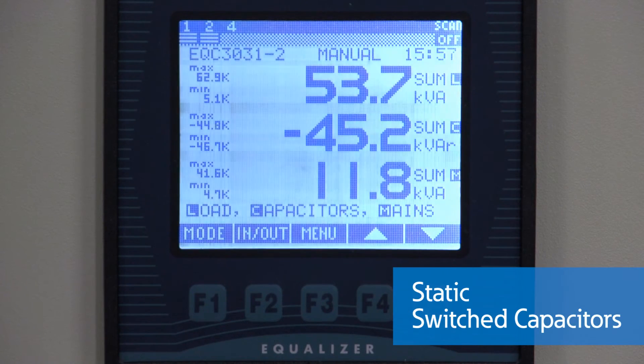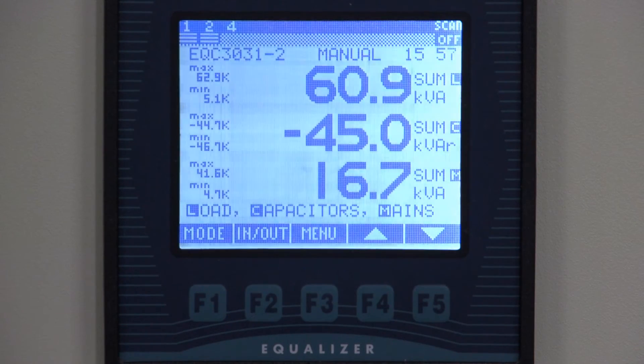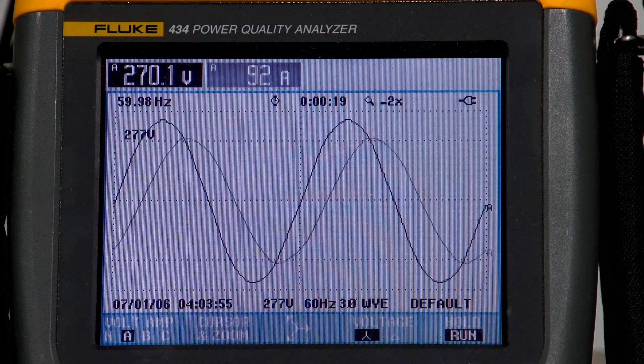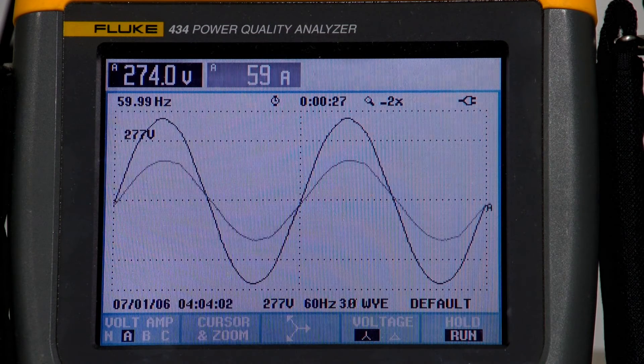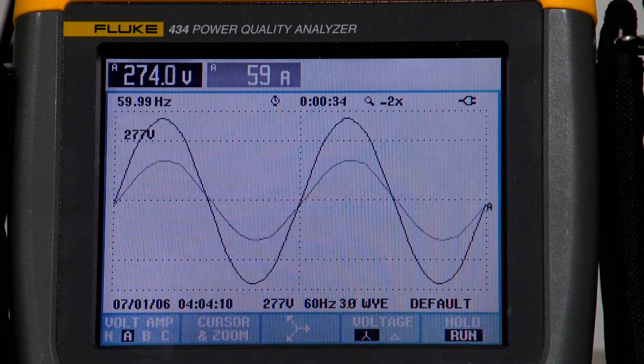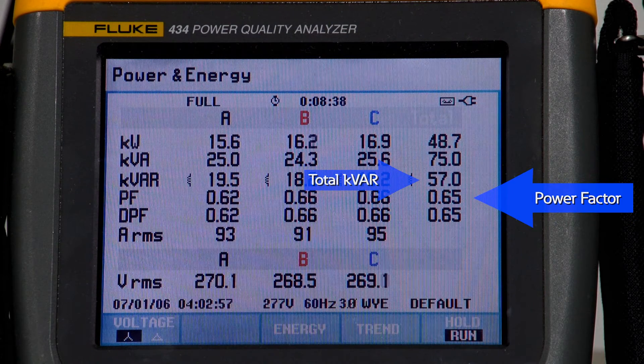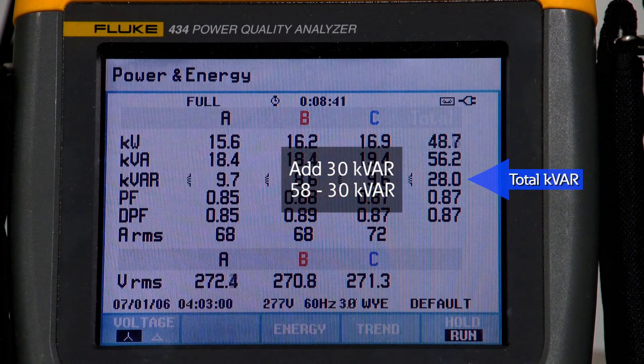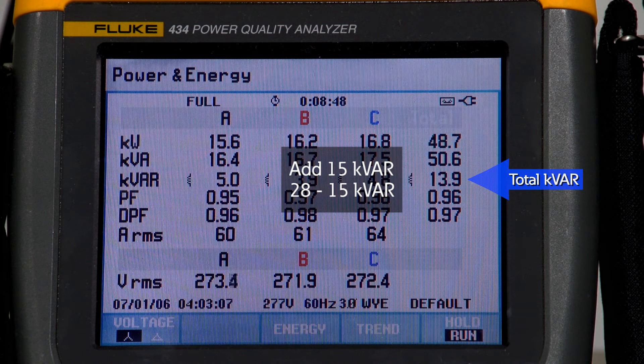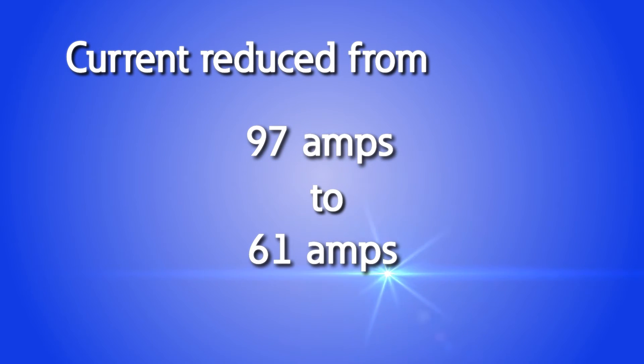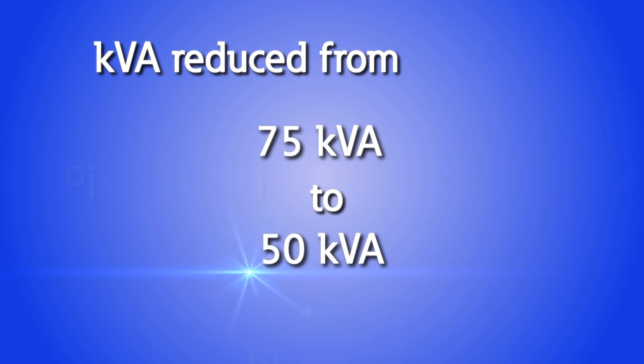For applications where faster response is required — like sawmills, car shredders, and other dynamic processes — our static switch capacitor banks are a perfect match and can respond within one electrical cycle. In this demonstration, we will show how simply adding capacitance to a system with a poor power factor can reduce your current and kVA while increasing your power factor. The power factor of this load starts at 0.65. By adding 30 kVAR of capacitance, the power factor increases to 0.87, and by adding an additional 15 kVAR, the power factor reaches 0.97. The net effect is that current was reduced from 97 amps to 61 amps, and kVA was reduced from 75 kVA to 50 kVA, freeing up capacity in the upstream cables and transformer.